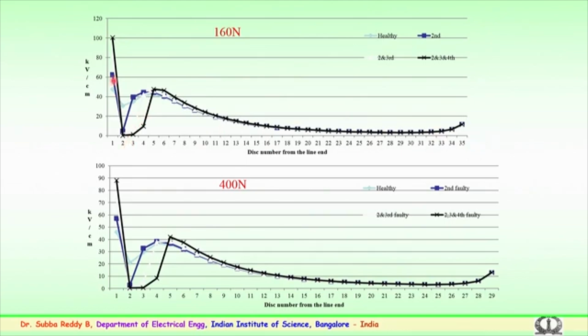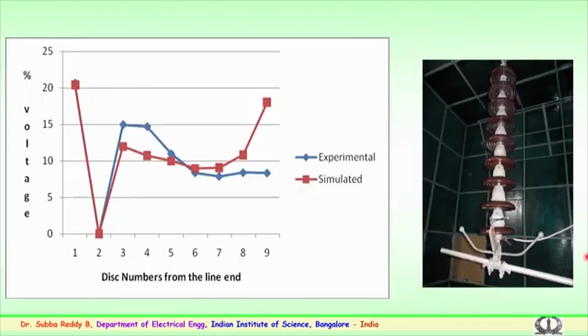Various fault conditions were simulated for 400 kilonewtons. This is again for 29 discs in a string of a 765 kV line. Again you can see how the field gets modified depending upon the insulator location where the faults are. You can see the second and third fault, and how the field gets modified here. The potential gets modified. You can see the green curve and the other faulty conditions. This gives important information.